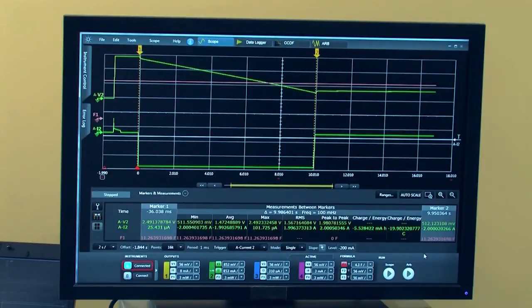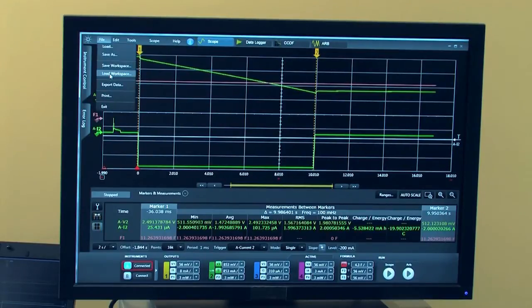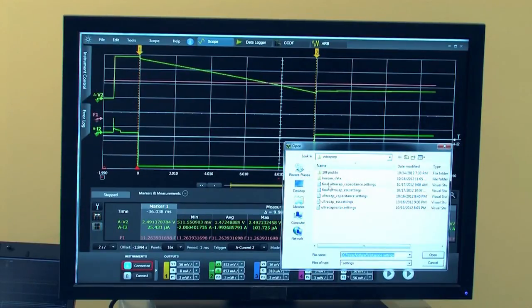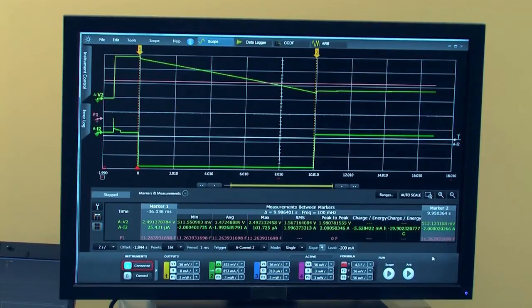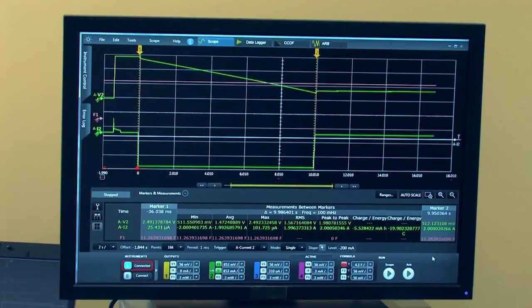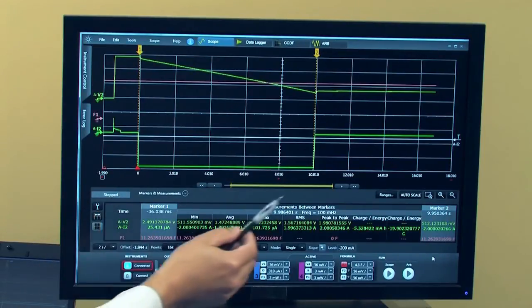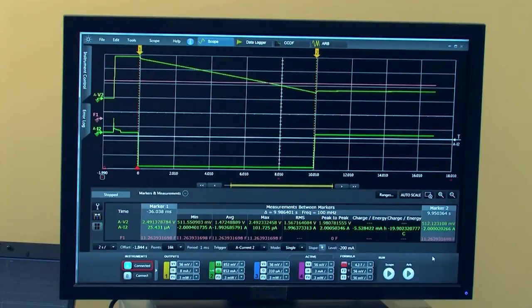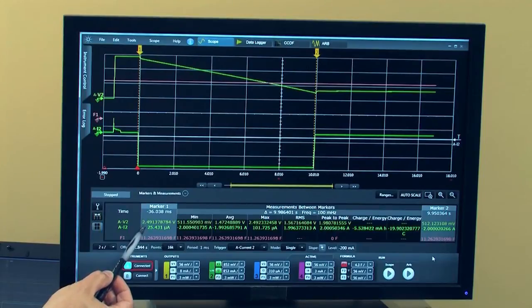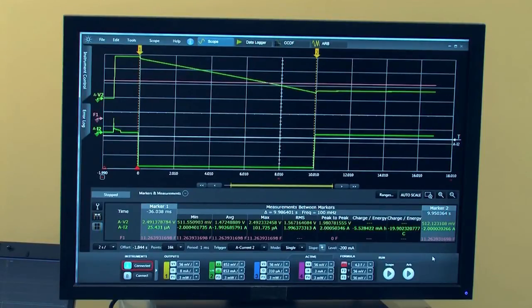Now I'm going to be loading the software workspace by going to File > Workspace and loading my saved profile that I had done prior. The markers are placed in such a way that they are selected based on the equation. Once you have that marker information, you'll be able to calculate the actual capacitance based on the formula.